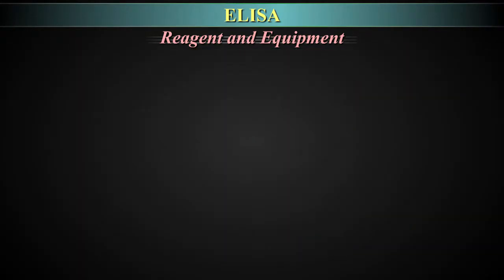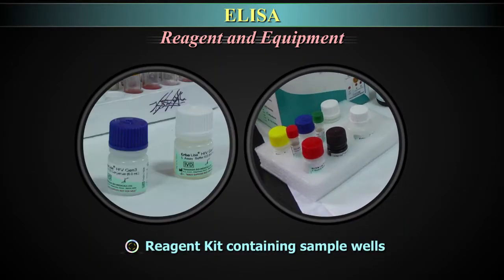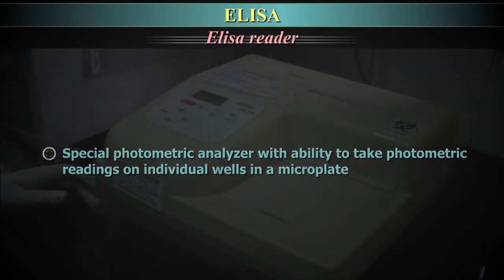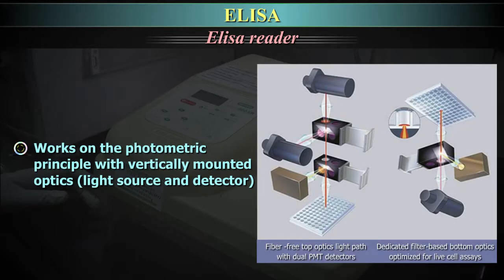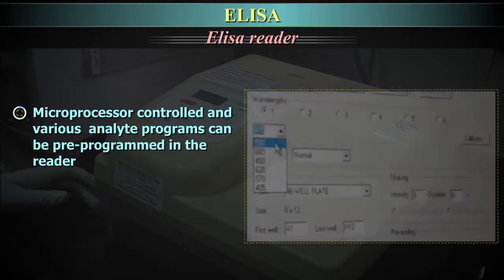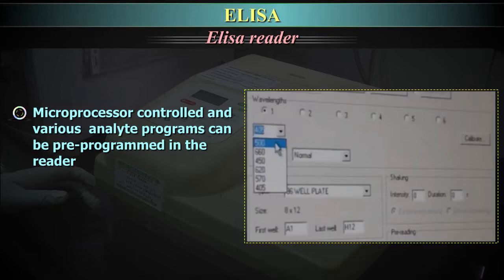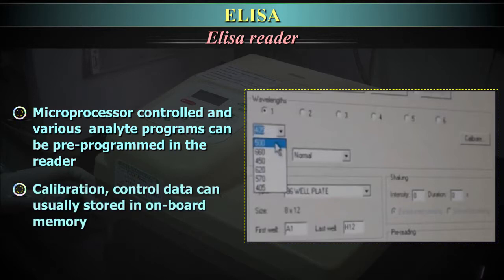Reagents and equipment required: ELISA reader, ELISA washer, pipette (multi-channel or single-channel), incubator, and reagent kit containing sample wells. ELISA readers are special photometric analyzers with the ability to take photometric readings on individual wells in a microplate. They work on the photometric principle with vertically mounted optics, light source and detector. Similar to a photometer, ELISA readers are microprocessor controlled and various analyte programs can be pre-programmed in the reader. Calibration control data can usually be stored in on-board memory.